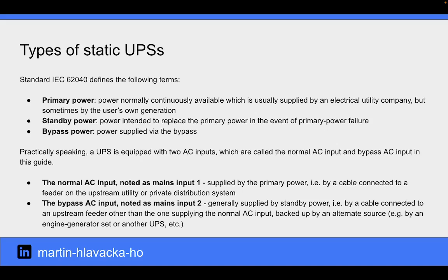Practically speaking, a UPS is equipped with two AC inputs, which are called the normal AC input and bypass AC input in this guide. The normal AC input, noted as mains input 1, is supplied by the primary power. The bypass AC input, noted as mains input 2, is generally supplied by standby power.